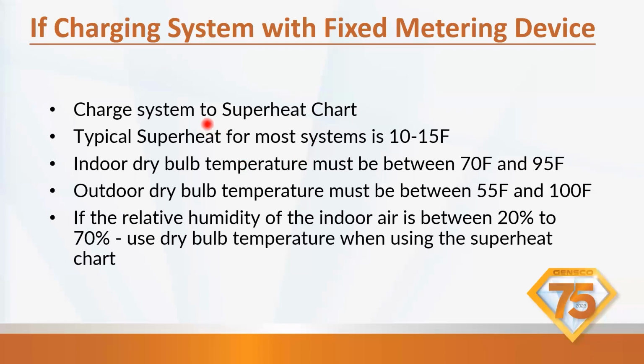You're going to charge a system with a fixed metering device. So this is geared towards orifices and pistons. So charge the system to the superheat chart. Your typical superheat for most systems is going to be between 10 to 15 degrees Fahrenheit. You're going to need your indoor dry bulb temperature, which must be between 70 and 95, because it's going to go off the cooling. Outdoor dry bulb temperature must be between 55 and 100. You have to meet those parameters to get an effective charge. If the relative humidity of the indoor system is between 20% to 70%, use dry bulb temperature when using the superheat chart.